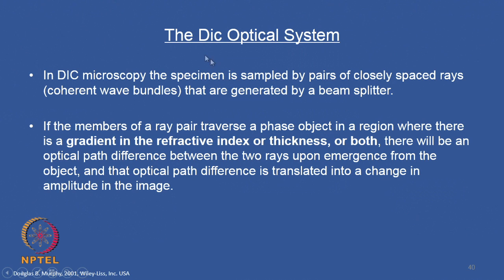We can appreciate how DIC improves contrast. In DIC microscopy, the specimen is sampled by pairs of closely spaced rays — coherent wave bundles generated by a beam splitter. If the ray pair traverses a phase object in a region where there is a gradient in refractive index or thickness or both, there will be an optical path difference between the two rays upon emergence from the object, and that optical path difference is translated into a change in amplitude in the image.